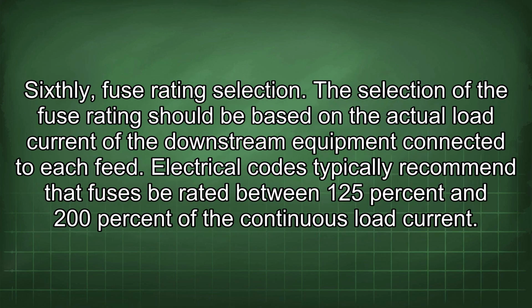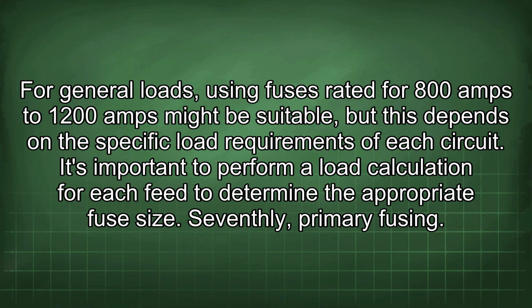Sixthly, fuse rating selection. The selection of the fuse rating should be based on the actual load current of the downstream equipment connected to each feed. Electrical codes typically recommend that fuses be rated between 125% and 200% of the continuous load current. For general loads, using fuses rated for 800 amps to 1200 amps might be suitable, but this depends on the specific load requirements of each circuit. It's important to perform a load calculation for each feed to determine the appropriate fuse size.